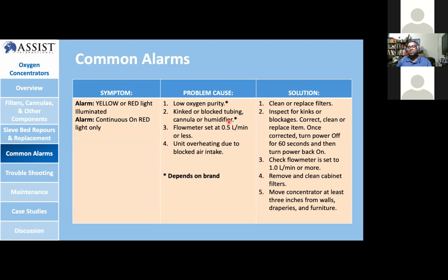Unit overheat due to a blocked air intake. So make sure you clean and replace the filter, inspect for kink blockage, check the flow is set to 1 liter per minute, and remove and clean the cabinet filter. Move the concentrator at least 3 inches or 1 meter away from the wall. So all these are very important. Sometimes you push it near to the wall and don't get flow.